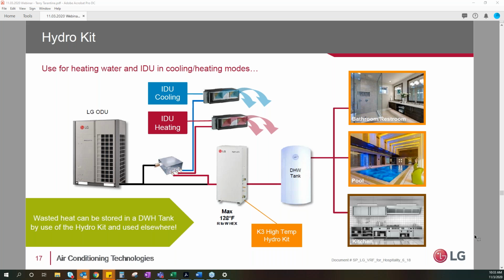And here they're just talking about some other options we have. We don't have to heat air. We can also use rejected heat to heat water. Here they're showing pools, kitchens, bathrooms will preheat water, take some of the load off of what we have for heating the water system, saving on gas or electricity. We've even seen some systems where we've done in-floor heat. Although that's a little bit more complicated design, that is becoming more popular as we go through.